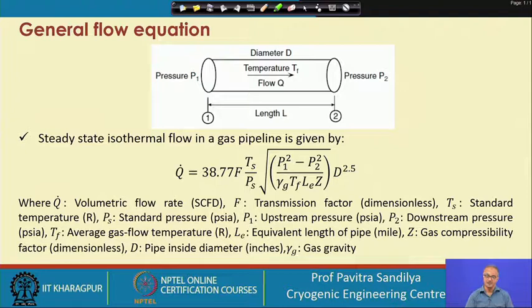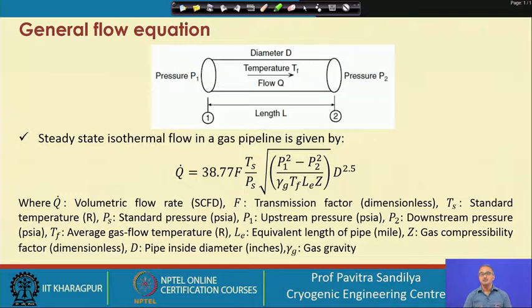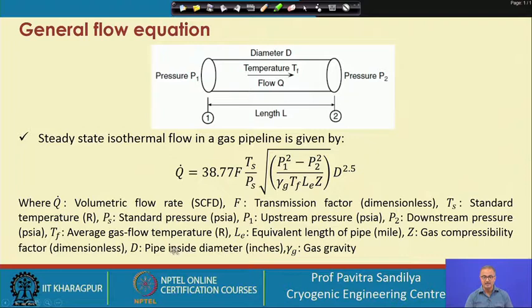There is a constant in the equation whose value changes depending on the unit system used — SI units or FPS (foot-pound-second, British units). The equation as presented uses FPS units where flow rate is in standard cubic feet per day, pressure is in PSIA (pounds per square inch absolute), temperature is in Rankine, pipeline length is in miles, and diameter is in inches. When using this equation, care must be taken to use these specific units to obtain the correct flow rate.